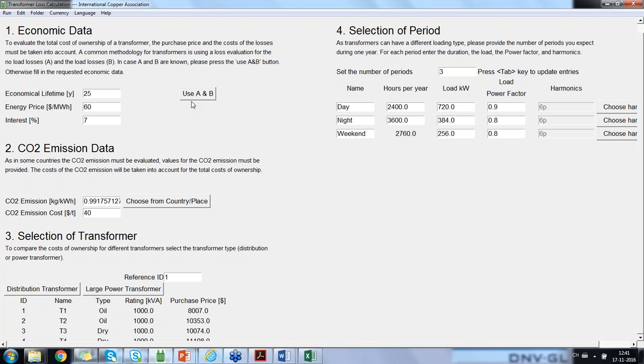Okay. So the next question is, what should be the vector group for mitigation of harmonics? That's a really tricky question. Normally, when you want to mitigate harmonic loading in transformers, you will very often see third and multiples of the third harmonics added to a loading, and in case you have a delta winding, they will be compensated within the transformer. Be careful. When I say compensated, it means that you will still have that harmonic within the windings of the transformer, so it will still heat up your transformer winding, while you don't see it on the outside of the transformer, only on the one side where you added those harmonics.